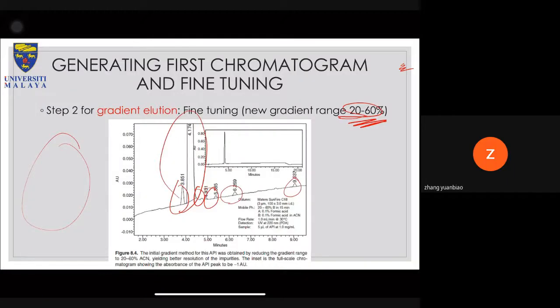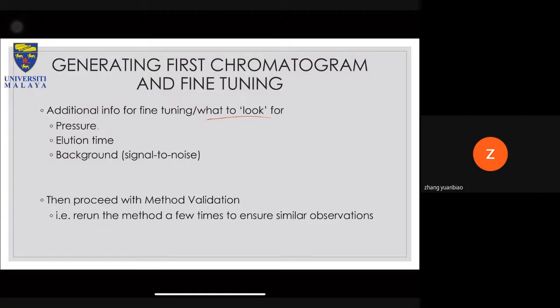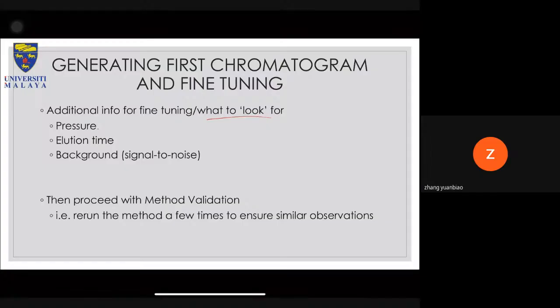Additional info for fine tuning and what to look for is the pressure, whether the pressure is too high or too low for your run. So there's no correct pressure for HPLC. It all depends on the equipment itself. Some equipment will run well at 200 psi. Some will be considered good at more than 10,000 psi, and so on and so forth. So it depends on the machine. That's why I didn't put any range. I just put it there.